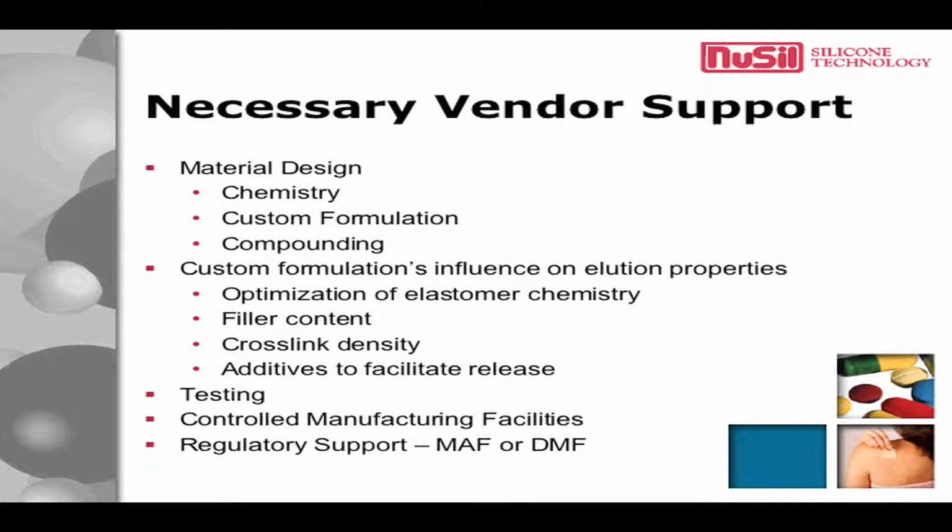Many things, if you're making an FDA submission, have to be documented. Your filler content, the cross-link density, any additives that have been added in addition to standard fillers, what type of testing, where's it manufactured, what type of regulatory support. It becomes a very complex thing, much more than just getting a simple, straightforward release profile or an elution profile.